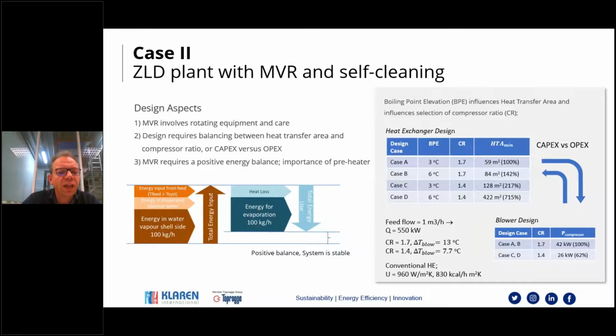The third element that I would like to describe is that it's important for an MVR that there is a positive energy balance, and that there's really this importance of the preheater. To illustrate that, we can have a look at the balance between energy input and energy use. So the energy input comes from the vapor that is condensing on the shell side. So there is a certain amount. Here the bottom block, energy in water vapor on the shell side.